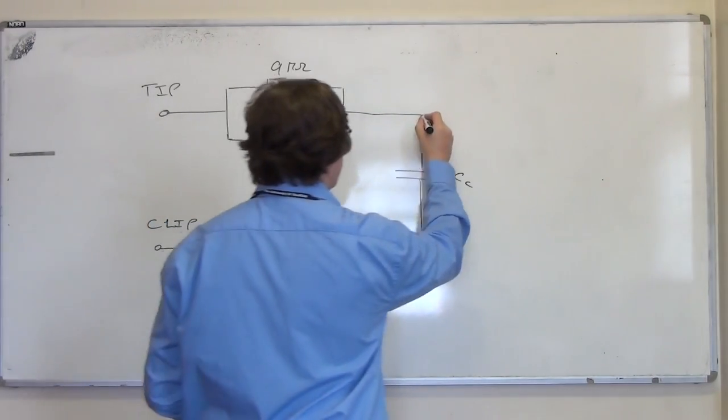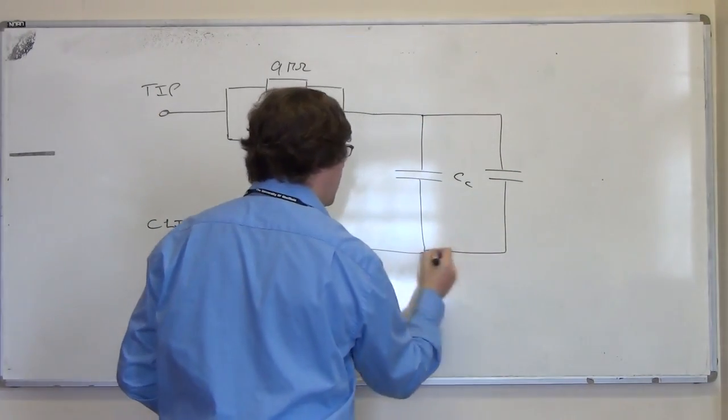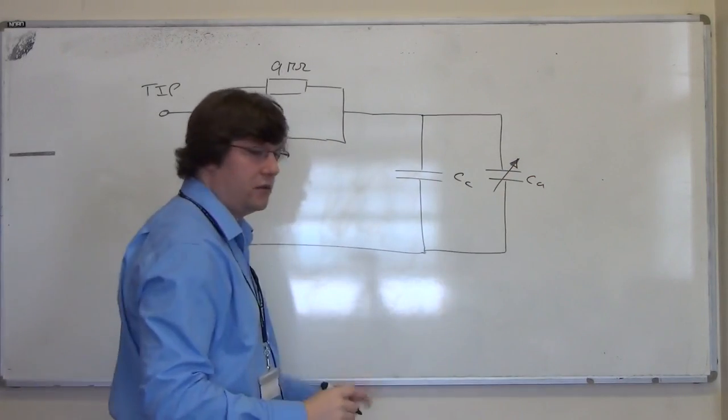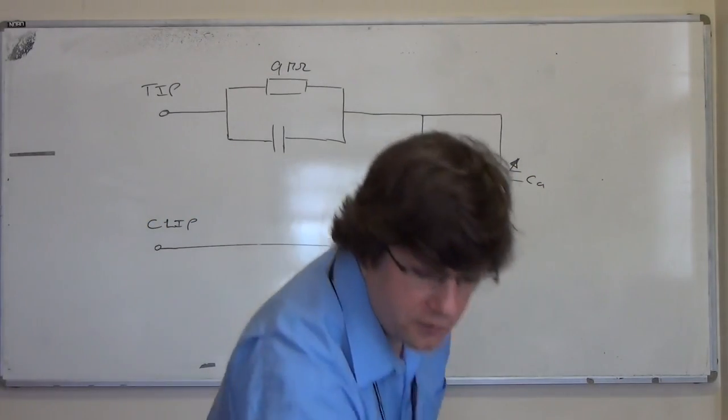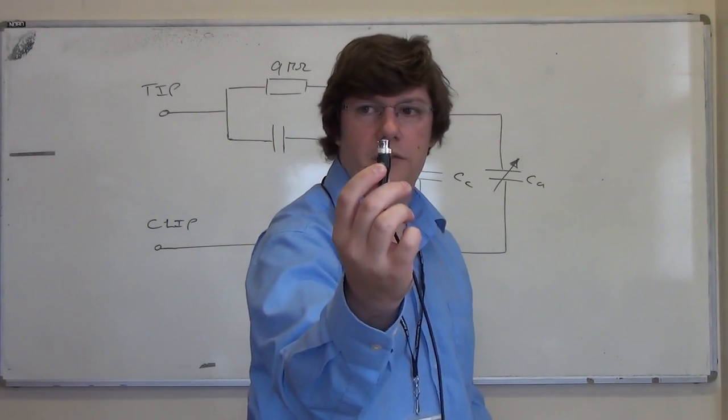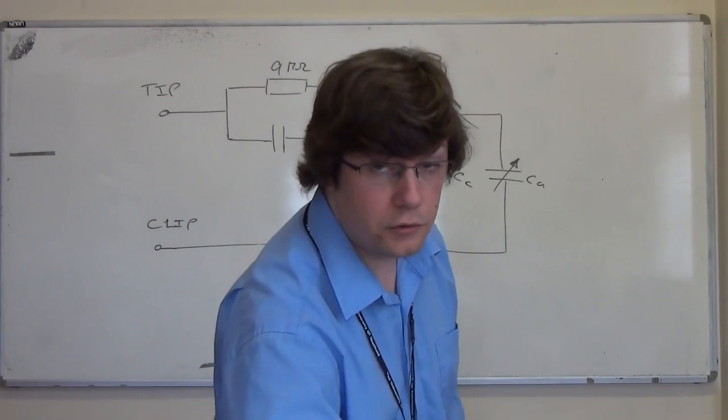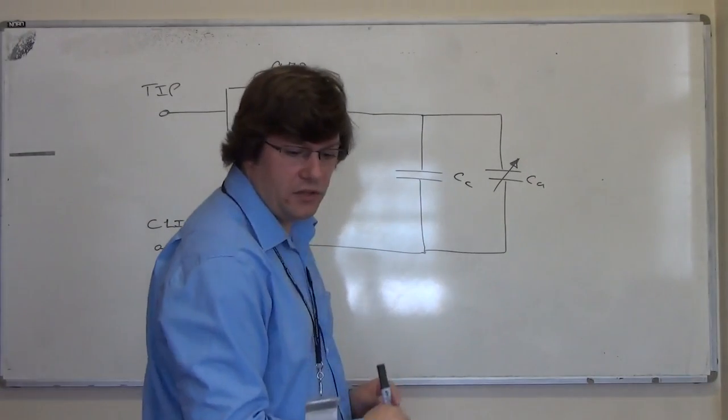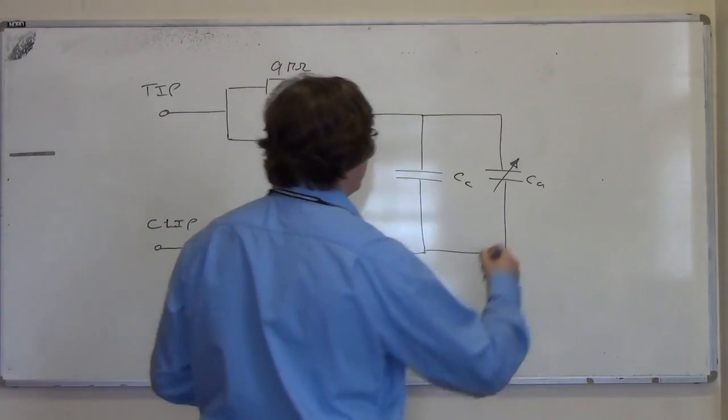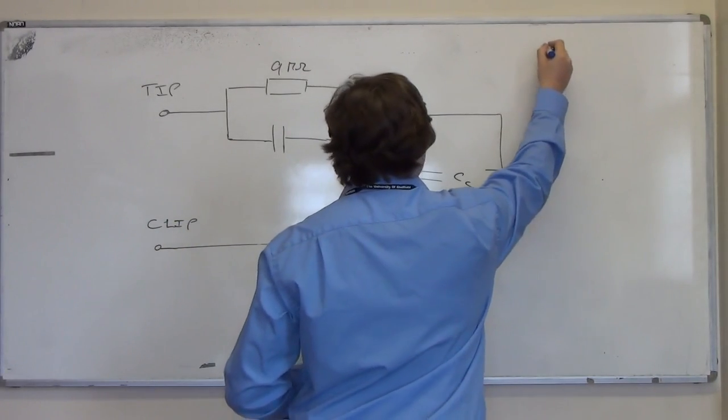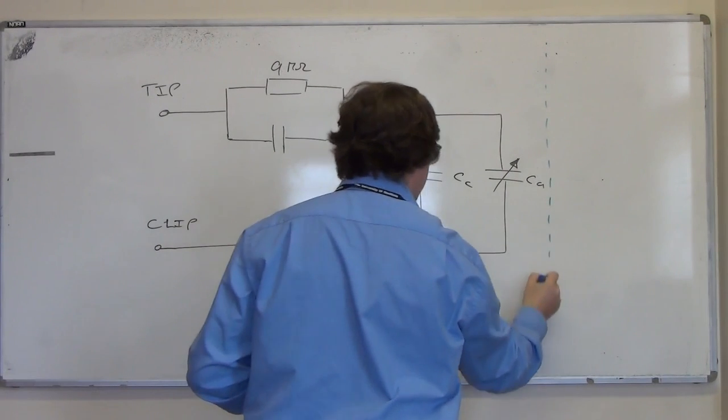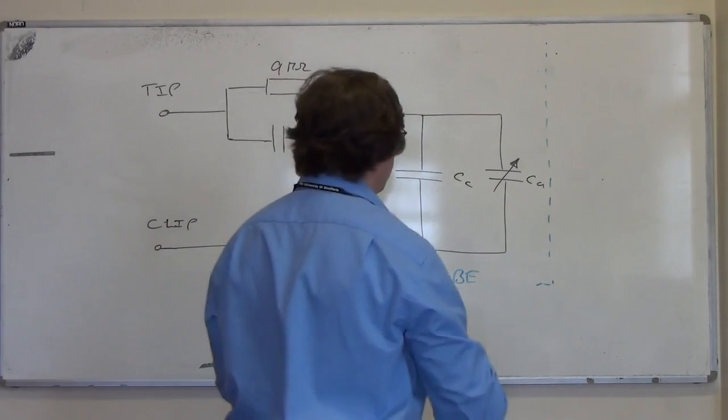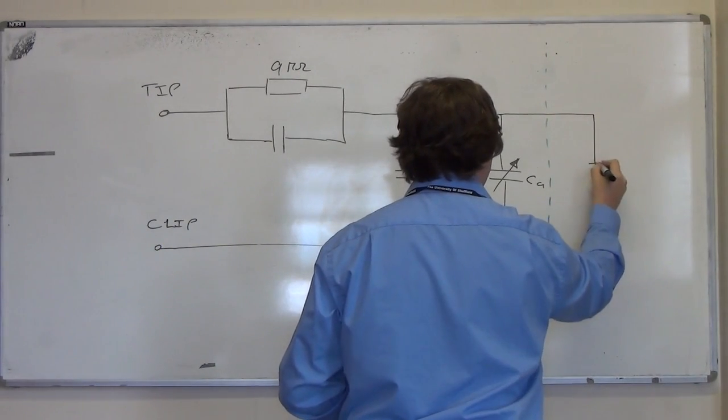There is another capacitance which is the one you are able to adjust. We'll call it Ca, and that turns up in parallel with the cabling capacitance. So this Ca is the capacitance you're tuning with the screwdriver. And then there is the oscilloscope which is attached to this. This is just the probe, and then we have the oscilloscope part.